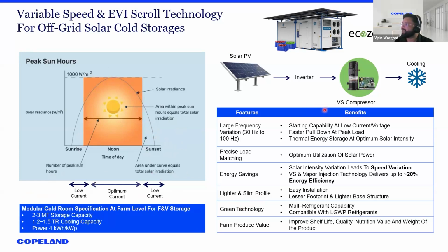The variable speed compressor, which can start at 67 volts with a lowest power supply and a frequency as low as 30 hertz, adds a lot of value because of the variation in power quality due to solar irradiance. That's actually helping to enhance the overall solution developed by Ecozen. The use of variable speed and vapor injection technology is definitely adding value and saving non-conventional energy produced by solar power by about 20%.